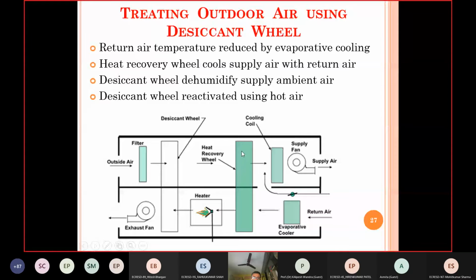Right? So this wheel is having some matrix material which is getting cooled here, and then it is delivering cooling here. It slowly rotates and goes in the opposite path of air. Right? Now, this air can be heated, and you are using it in a desiccant wheel, and here you are removing the moisture from air. So this wheel contains the desiccant material, and because of that the moisture from outside air is absorbed here.